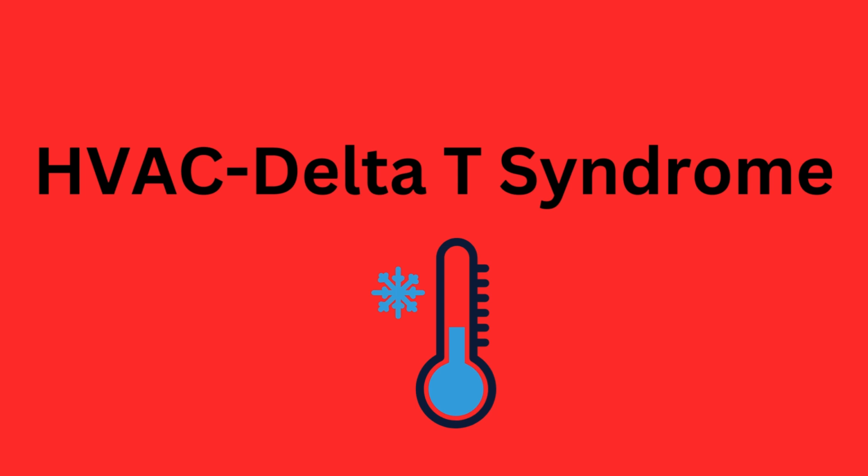A typical delta T range for HVAC systems is around 16 to 22 degrees Fahrenheit, 9 to 12 degrees Celsius. Values outside this range may indicate potential issues that need addressing.